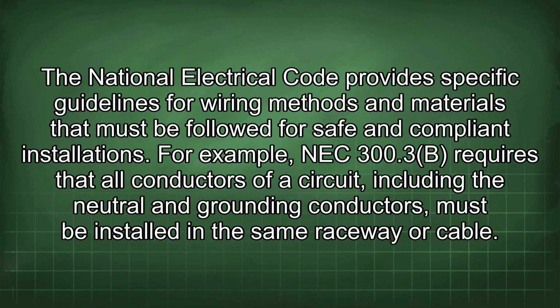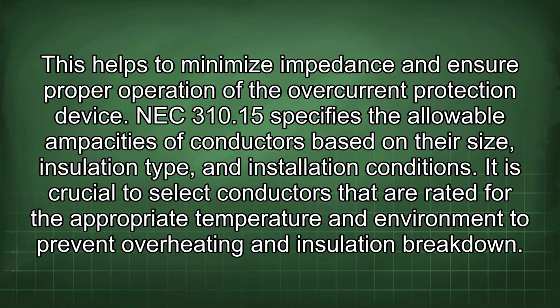The National Electrical Code provides specific guidelines for wiring methods and materials that must be followed for safe and compliant installations. For example, NEC 300.3(B) requires that all conductors of a circuit, including the neutral and grounding conductors, must be installed in the same raceway or cable. This helps to minimize impedance and ensure proper operation of the overcurrent protection device.